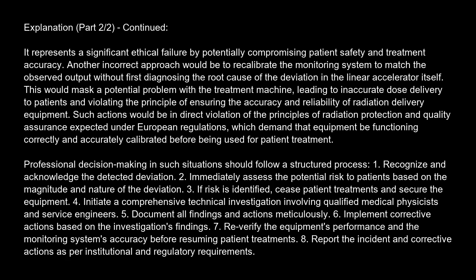Professional decision-making in such situations should follow a structured process. 1. Recognize and acknowledge the detected deviation. 2. Immediately assess the potential risk to patients based on the magnitude and nature of the deviation. 3. If risk is identified, cease patient treatments and secure the equipment. 4. Initiate a comprehensive technical investigation involving qualified medical physicists and service engineers. 5. Document all findings and actions meticulously. 6. Implement corrective actions based on the investigation's findings. 7. Re-verify the equipment's performance and the monitoring system's accuracy before resuming patient treatments. 8. Report the incident and corrective actions as per institutional and regulatory requirements.